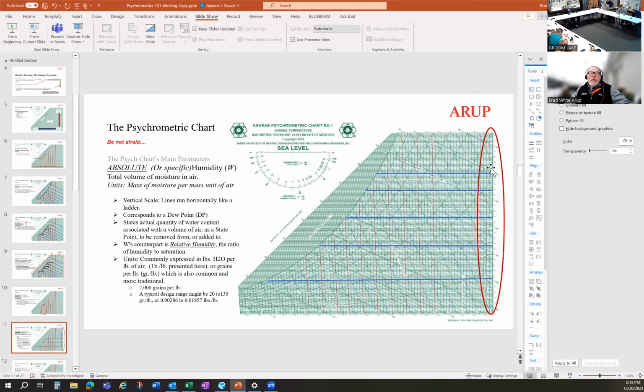Those grains per pound are read on the right-hand scale of the psych chart, and from there you can read straight across. Any line that's directly horizontal represents different temperature but more or less the same humidity. The higher these bars are, the more humidity, but these are all at a constant temperature line.